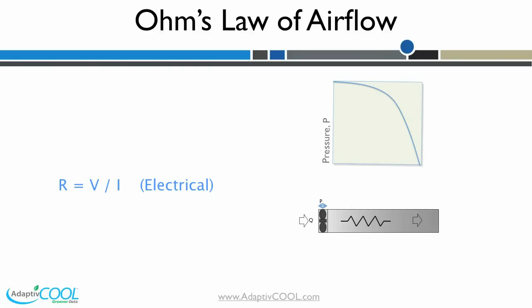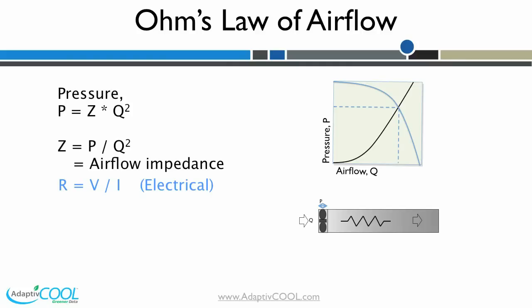It is observed that the pressure created by the fan is proportional to the square of volumetric airflow through the duct. That is, for a given duct, P divided by Q squared is a constant — we call it Z — the airflow impedance. So voltage, current, and resistance in the electrical domain are equivalent to pressure, volumetric flow, and impedance in the airflow domain.